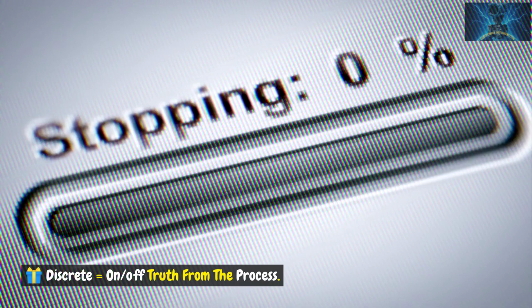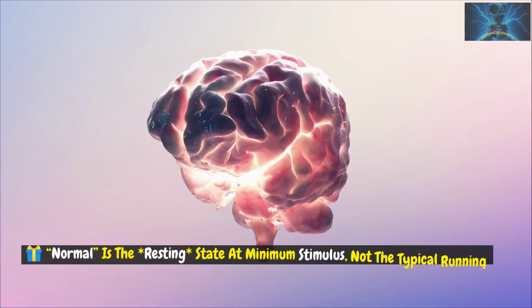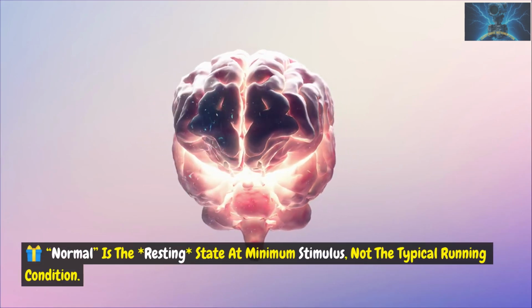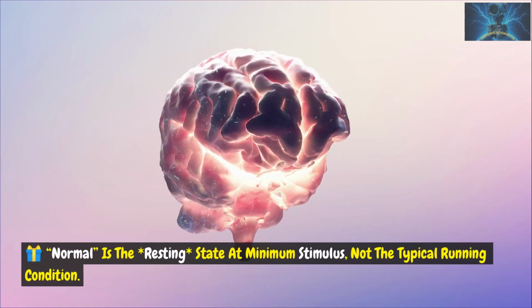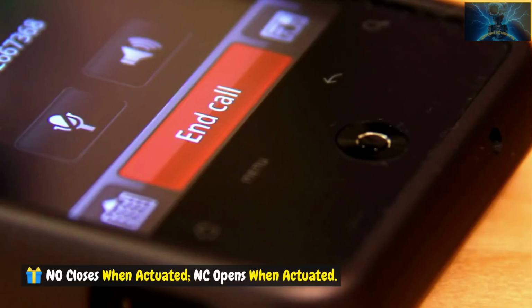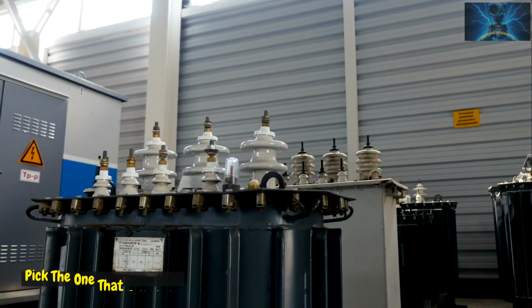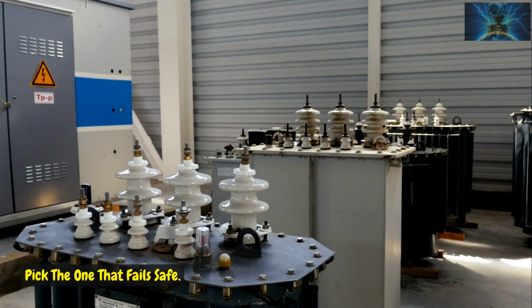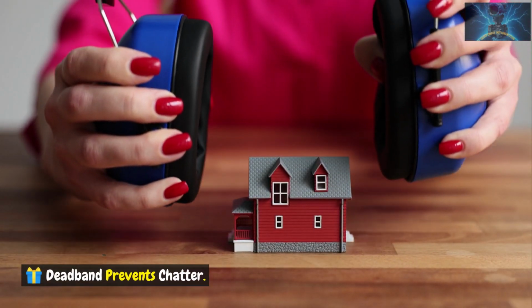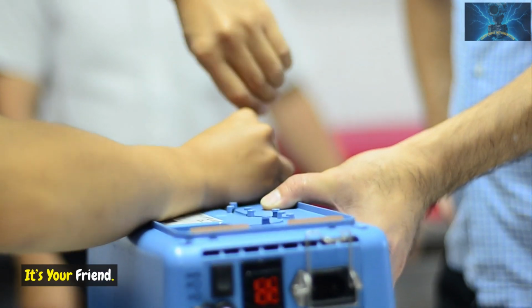Takeaways, discrete and on-off truth from the process. Normal is the resting state at minimum stimulus, not the typical running condition. NO closes when actuated. NC opens when actuated. Pick the one that fails safe. Deadband prevents chatter. It's your friend.